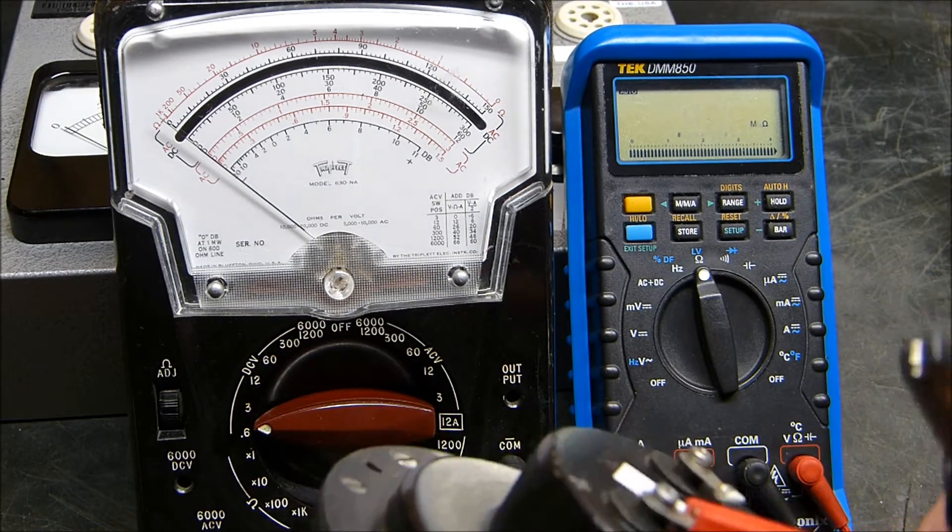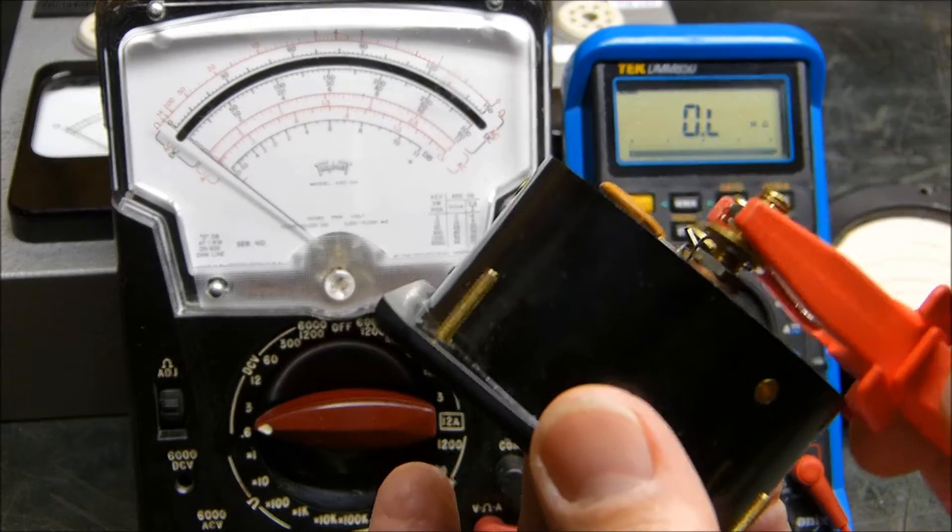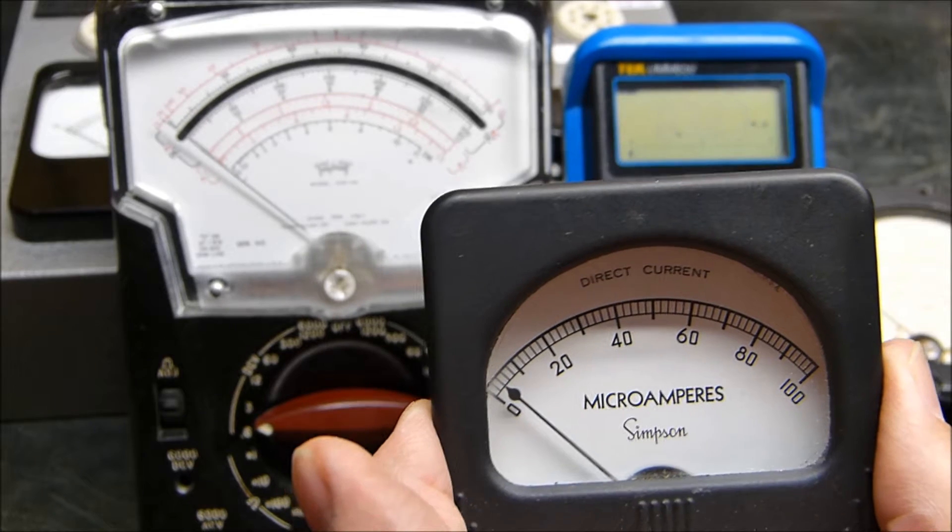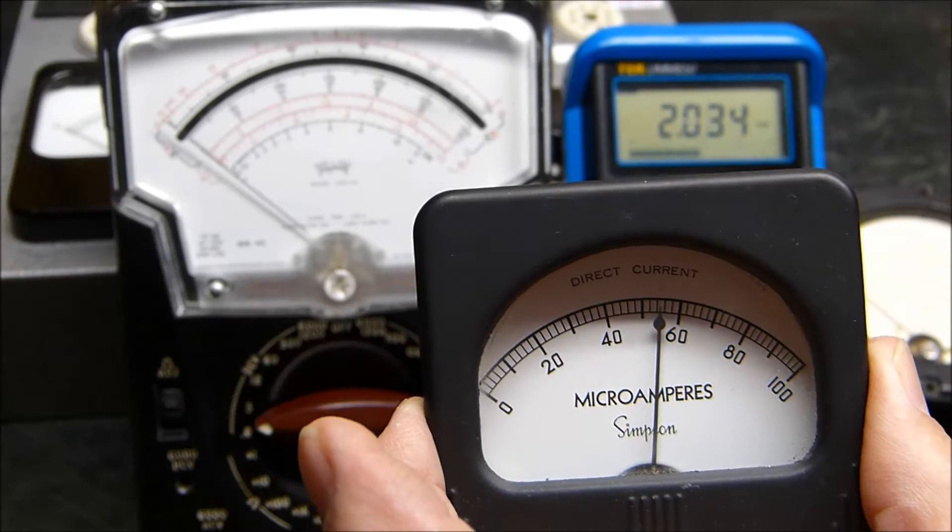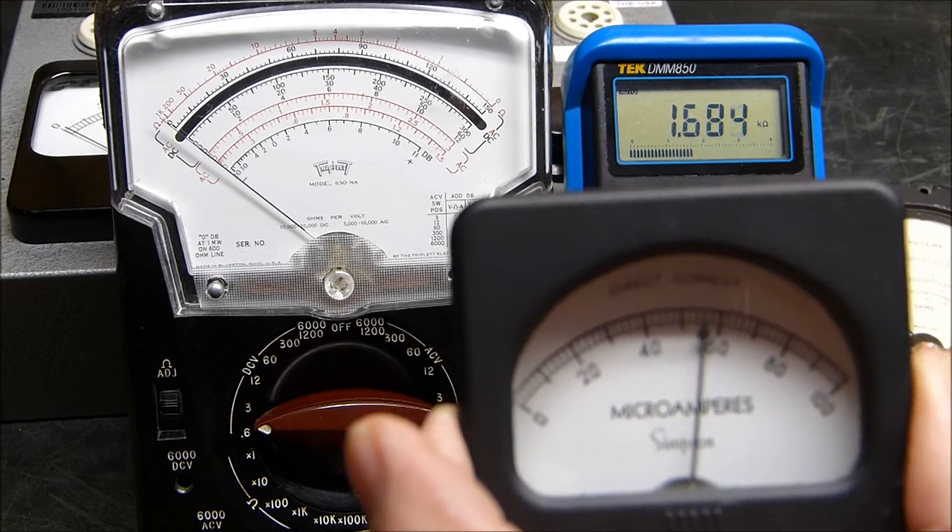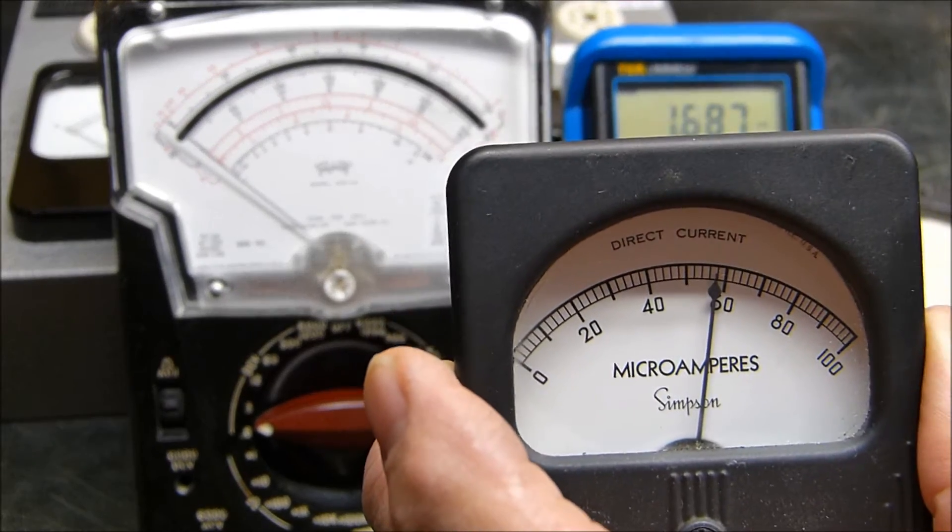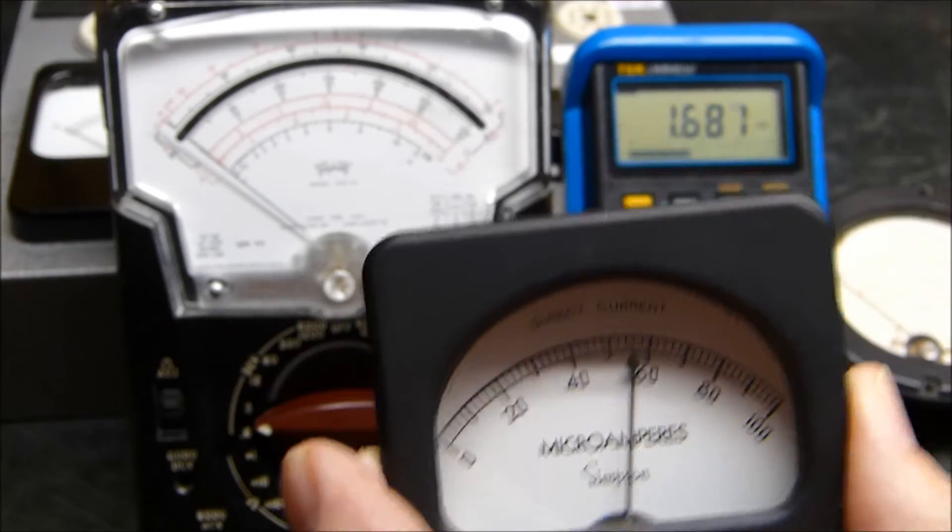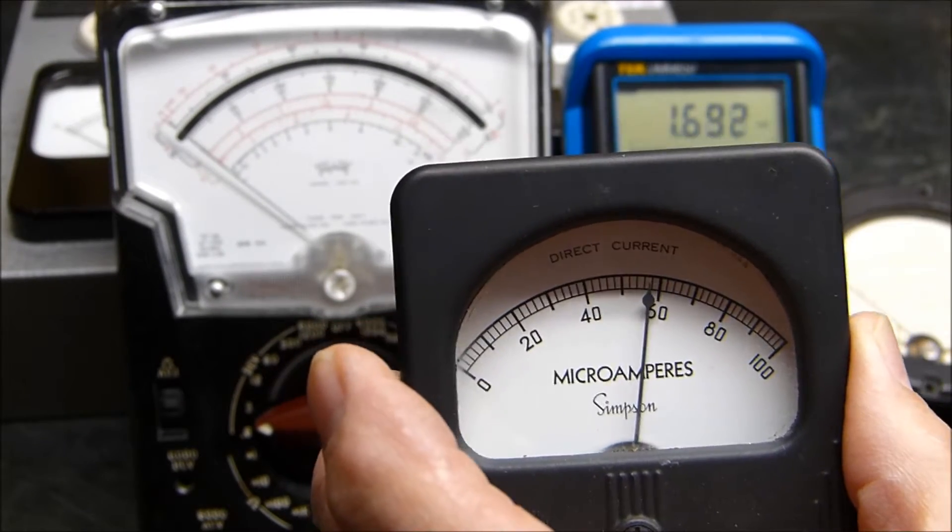This one, 100 microamp, let's put it across there and watch what happens. It thinks about it a while, reads about half scale, and reads 1.8K, 1800 ohms, can't make up its mind. Well, this is a 2500 ohm meter, so you get a bogus reading even though you have high dollar equipment. You just can't quite figure it out.